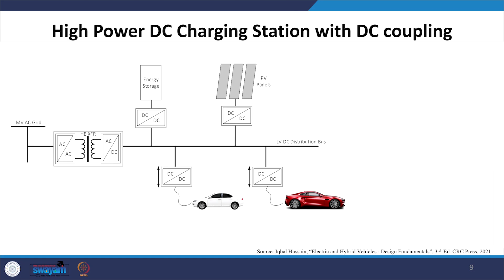So one can implement a power architecture which has a high frequency transformer. Again, it is a greater than 11 kV 3 phase system. We can convert that low frequency, which is a 50 hertz or 60 hertz line, to high frequency AC. It is the high frequency AC which is seen by the transformer, and from this one you will again convert into high frequency AC, and from high frequency AC one can easily convert into DC and then create the low voltage DC distribution. Then you can integrate energy storage as well as PV just by putting the DC DC converter into the low voltage distribution bus.